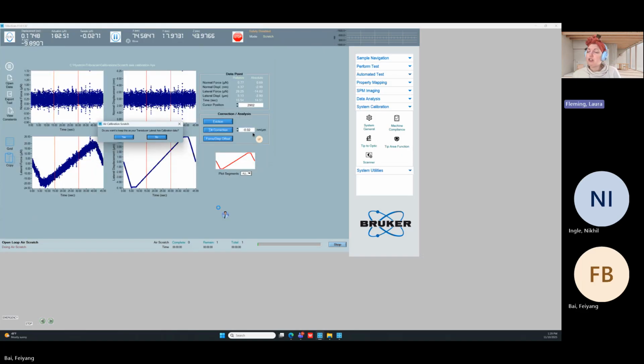Now we also get our first view of the scratch analysis screen. In this screen, you get 4 graphs. Let's go clockwise: you get normal force, normal displacement, lateral force, and lateral displacement. Keep in mind we had programmed the normal force and the lateral displacement. So my first thing I always do for every scratch, whether it's a Cal Air scratch or any standard one, is ask: did it do what I asked it to do? What I asked it to do was have 0 force in the normal direction, and then move back 5, forward 10, and then back 5. So did it do both of those things? It did.